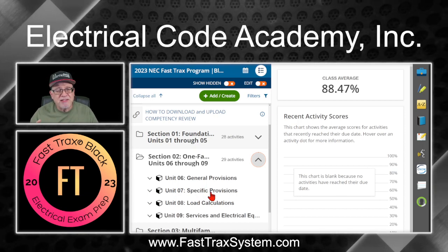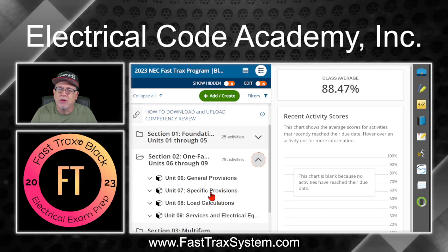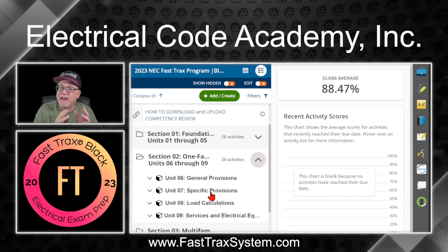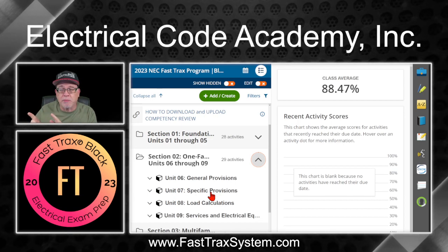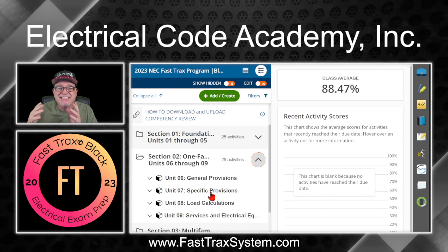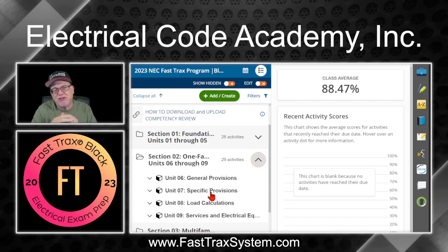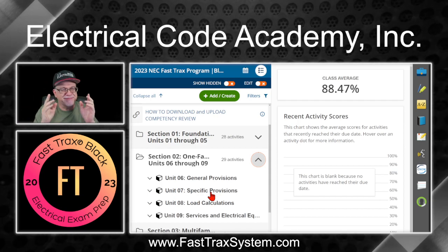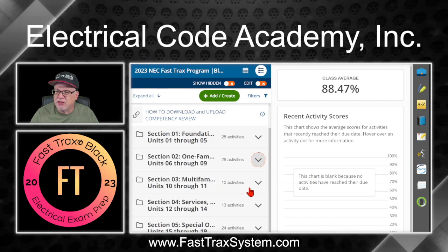Obviously, for sizing the grounded neutral conductor, you need to use the standard method because 220.61 is inside of Part 3. That's the standard method. When you go to the optional method, which is Part 4 in Article 220, it doesn't give you any direction for the grounded conductor sizing. So that's why you've got to go to 220.61, and that is under Part 3. Trust me, in our program, you will learn all that. All right, so then we take you through that.